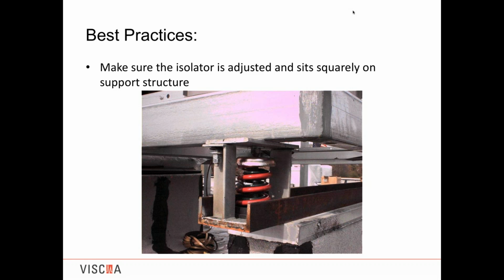As I had mentioned before, you don't remove any spacers until you can remove all of them. This is an issue where the spacer was removed and the other isolator was adjusted, and you can see the top plate of this isolator touching the lower housing. The spring hasn't been adjusted and nothing's happening, so you do not have vibration isolation.